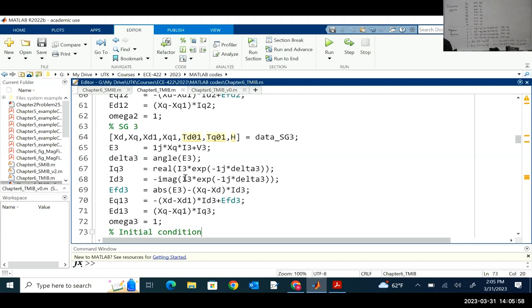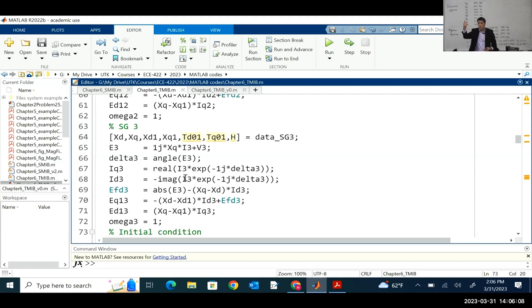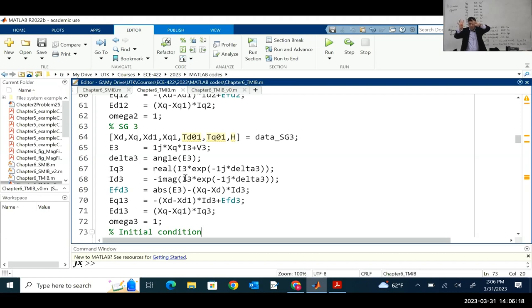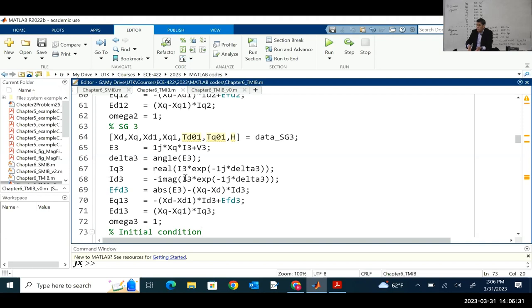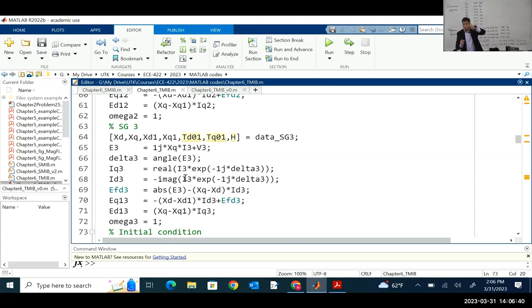EQ prime, ED prime — we're missing two: delta and omega. So EQ prime, ED prime, delta, and omega are the state variables; IQ and ID are the two algebraic variables. For generator three: another four state variables and two algebraic variables. For the grid, represented through algebraic equations — it's a four-bus system, one is the infinite bus, so we have three complex voltages, which gives us six variables.